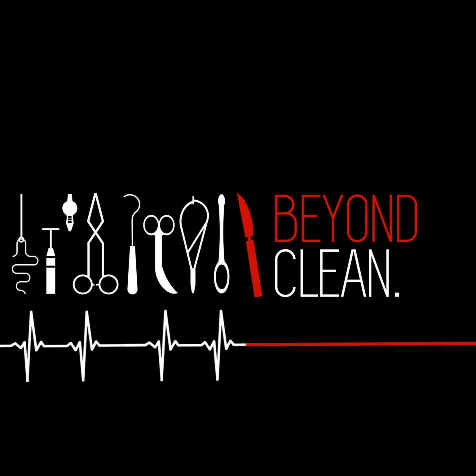But when you start adding chemistry to a device that can leach, they may not leach before sterilization, but let's expose it to heat, humidity, and now you can have increased leachables. And by the way, that's not just for colorants, that's for anything. Sterilization can have an impact on the leachability of a medical device. And cleaning, either taking away or adding to those. So when we've assessed the risk of a device, we have to look at it in its final form, because all those processes can impact what comes off a medical device.